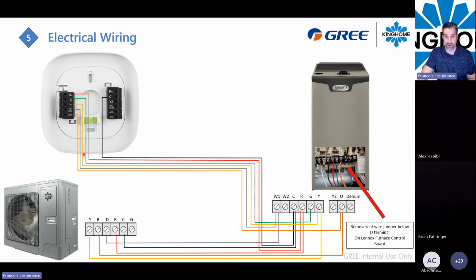And also for your W1, it will be hooked directly on the W1 of your furnace. Also you can use the D terminal connected on W1, so the unit will do the defrost, okay? Regarding the balance point you will use, if you manage the system to not use the heat pump in very low temperature, and the defrost will take around 1 minute or whatever, at some point maybe you don't have to connect the D terminal.